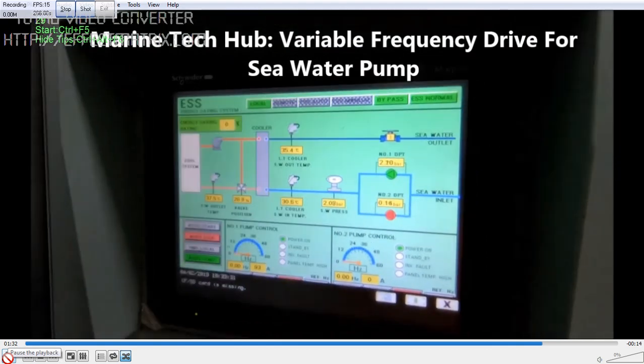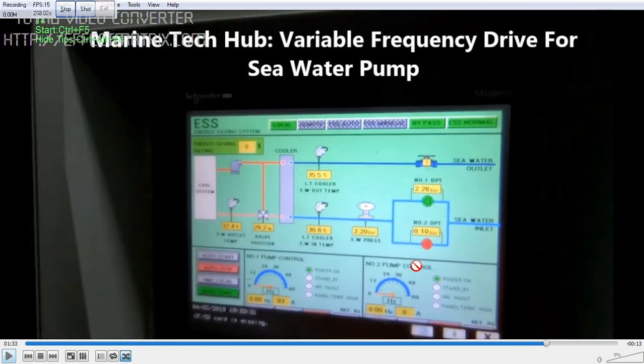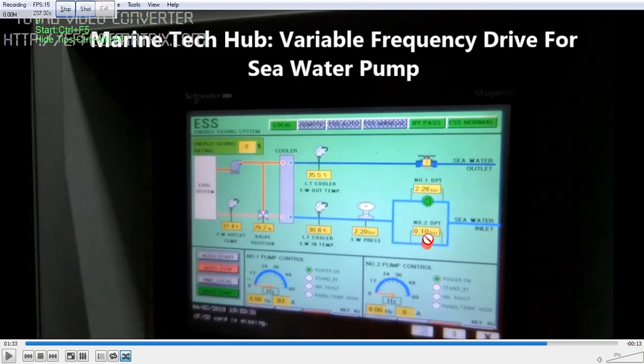This is the control panel where you can use it for controlling the RPM of the pump. You can see pump 1 is running and pump 2 is not running. You have the cooler, so sea water is pushed through the cooler. We are keeping the RPM less or more by adjusting the frequency — when the frequency is more, means more RPM; less means less RPM. This is sensed by the temperature — the temperature is set, and accordingly the sea water will flow through the cooler and maintain the temperature.